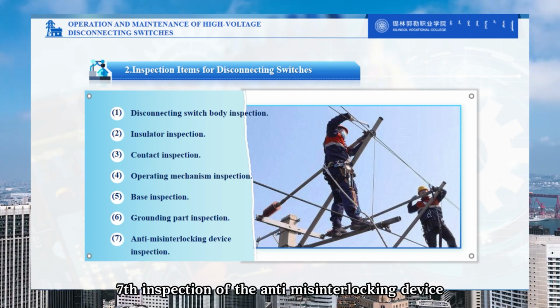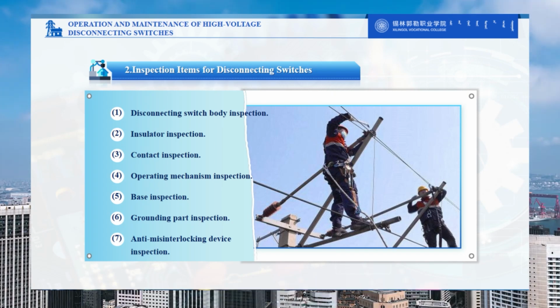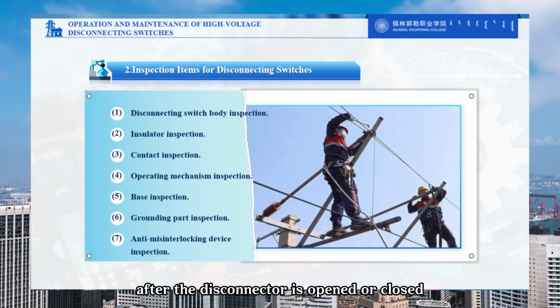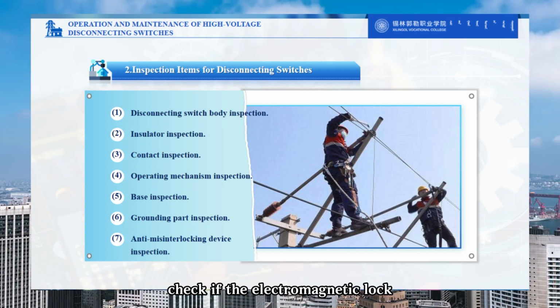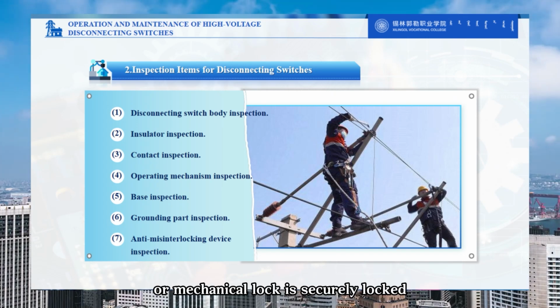Seventh, inspection of the anti-misoperation interlocking device. After the disconnector is opened or closed, check if the electromagnetic lock or mechanical lock is securely locked.